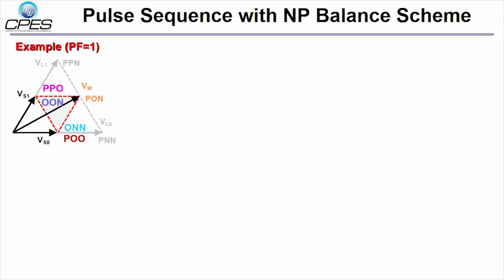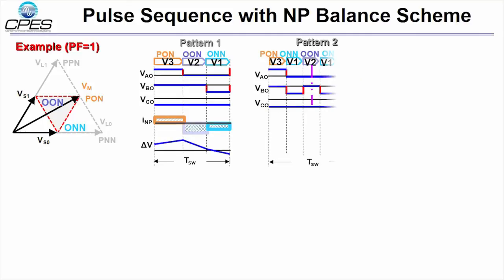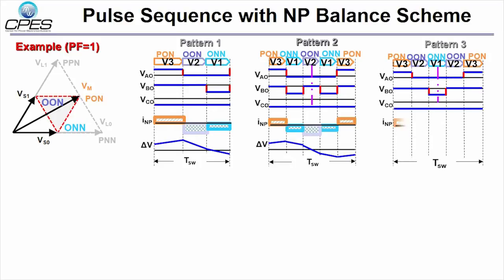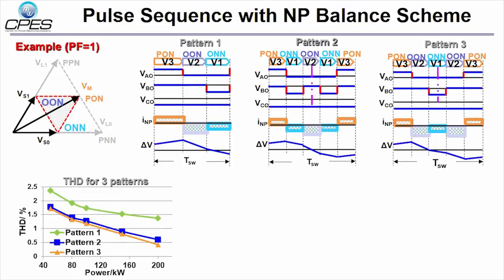The selected switching status can result in different pulse sequence patterns. Pattern 1 is asymmetrical sequence, and pattern 2 is symmetrical sequence with multiple switching events. Pattern 3 is symmetrical sequence with least switching events. The THD comparison shows that symmetrical sequence has smaller THD.